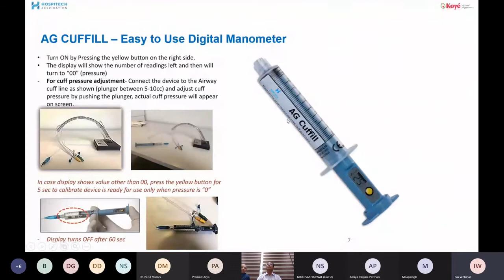Now, this device is easy to calibrate also. You don't have to send it out for any calibrations. When you switch on by pressing this yellow button, the first display that you see would be the number of readings which are remaining. The second display would be 00, indicating the device is ready for use. If you get any other number other than 00, it means the device requires calibration. All you have to do is wait for the device to switch off automatically after 60 seconds. Hold the yellow button down for more than 5 seconds after that. The LCD display will blink and display 00, indicating that calibration has been successfully completed.